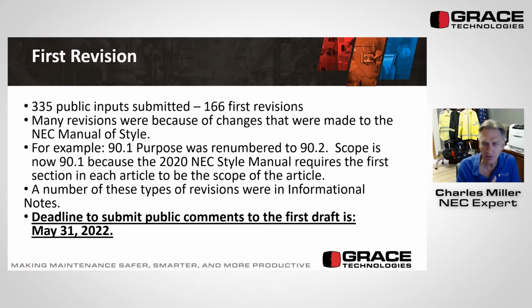The National Electrical Code and NFPA 70E have what's called a manual of style, meaning the document has to be laid out a certain way and worded a certain way. One of the things added to the manual of style for the NEC and 70E was that every article had to have a scope. A lot of articles in 70E didn't have one. For example, 90.1 Purpose was renumbered to 90.2 because a scope was added to the document, as required by the 2020 NEC style manual, which requires the first section of each article to have a scope.